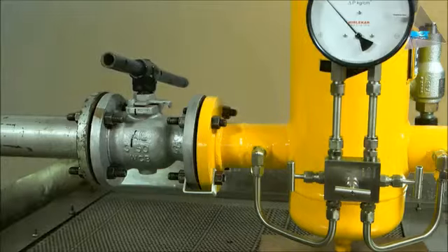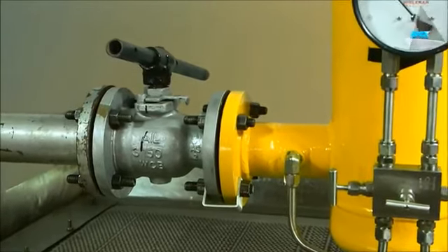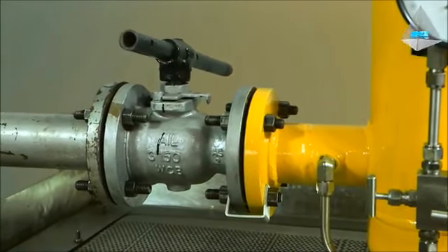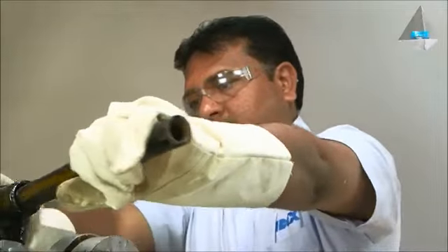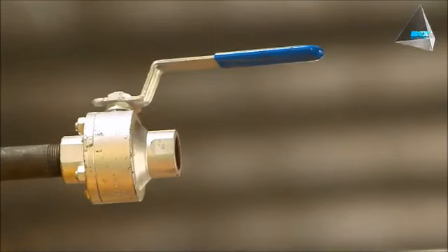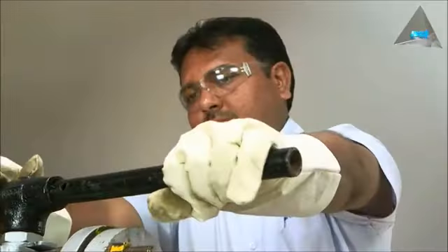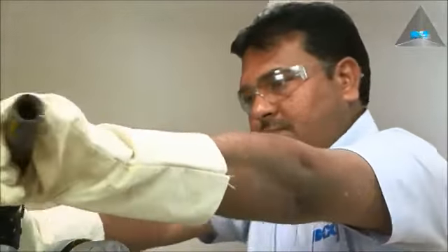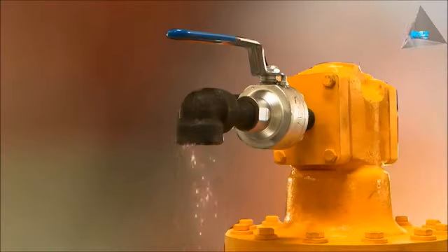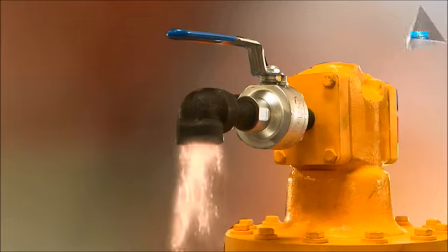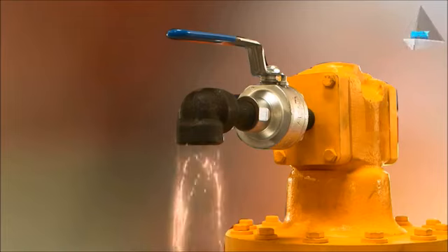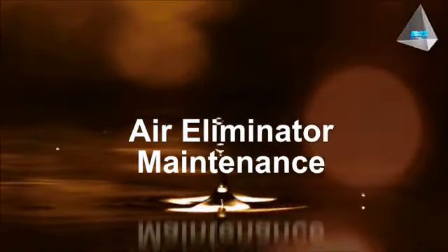Air eliminator commissioning. Close the manual valves located at the outlet and inlet of the air eliminator. Start the pump. Open the inlet valve slowly and allow the air to bleed through the vent. Once air stops coming from the vent, open the outlet valve. If care is not taken, a sudden rush of liquid may cause damage to the float. During initial operation, due to the mixture of air and liquid, some product will come out from the vent. This is not leakage.